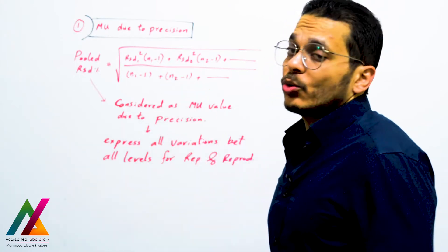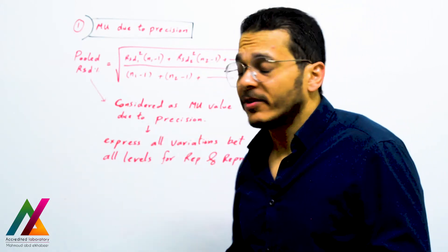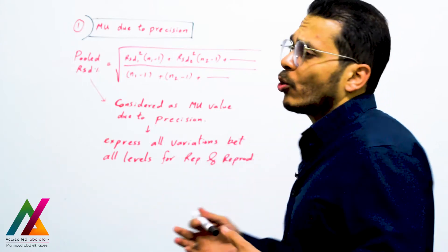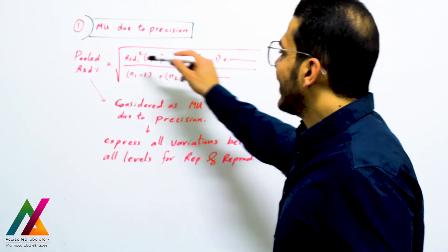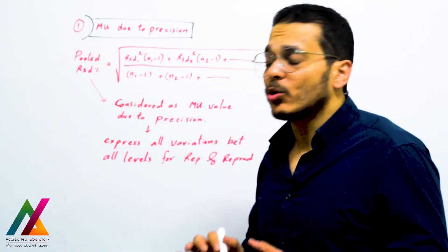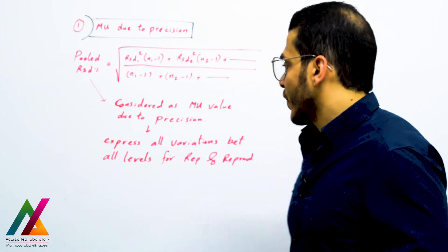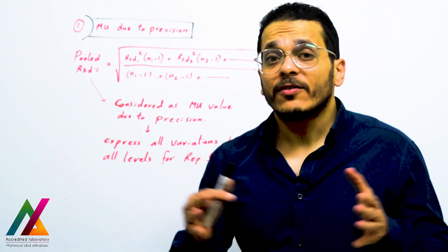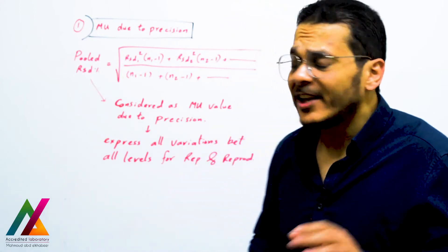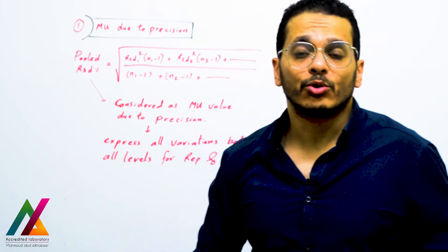From these relative standard deviations you calculate the pooled relative standard deviation, equal to the square root of: (RSD1² × (n1−1) + RSD2² × (n2−1) + ...) divided by the sum of the degrees of freedom for all levels. This pooled relative standard deviation is considered the measurement uncertainty value due to precision, because it expresses all variations coming from every step of measurement at both short and long time scales, covering repeatability and reproducibility.